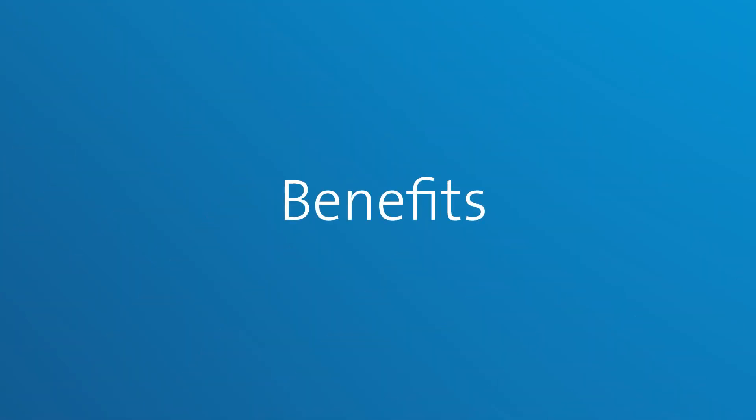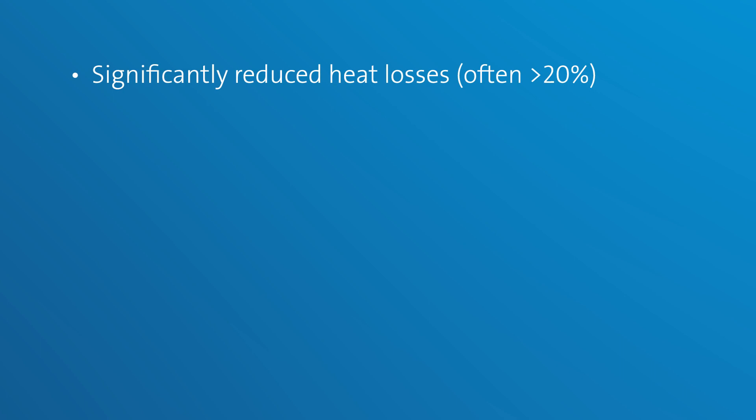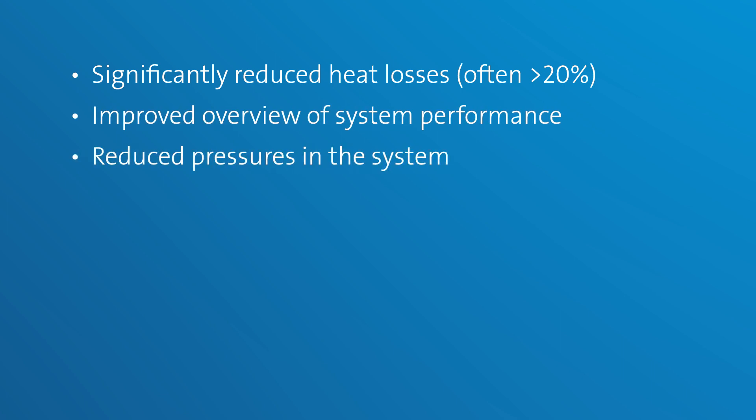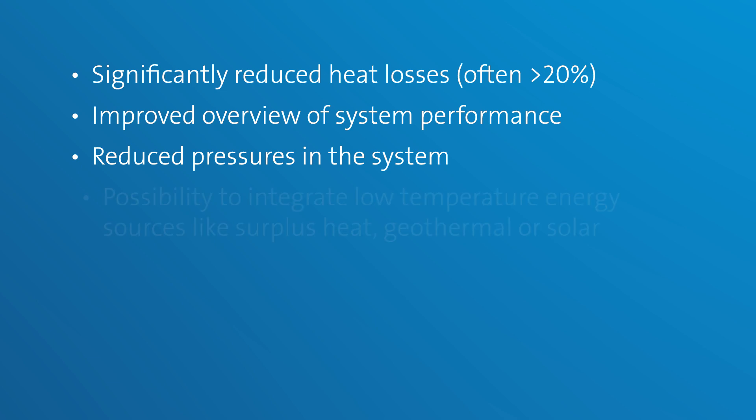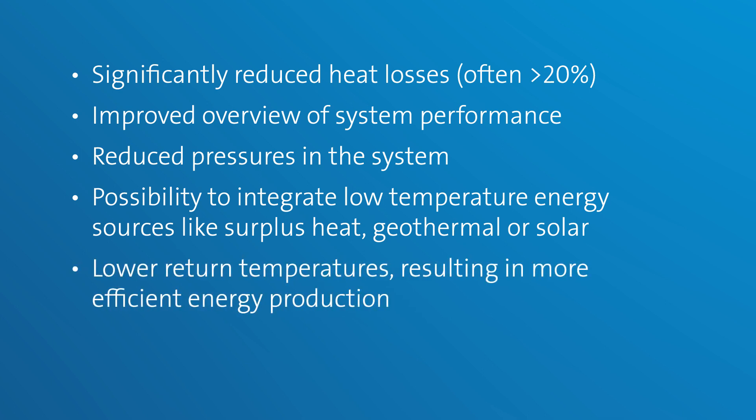Let's sum up the benefits. Significantly reduced heat losses, often greater than 20%. Improved overview of system performance. Reduced pressures in the system. Possibility to integrate low temperature energy sources like surplus heat, geothermal or solar. Lower return temperatures resulting in more efficient energy production. Best possible comfort for the consumers.